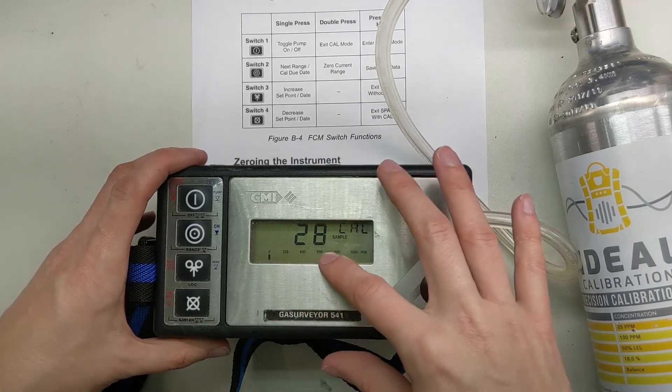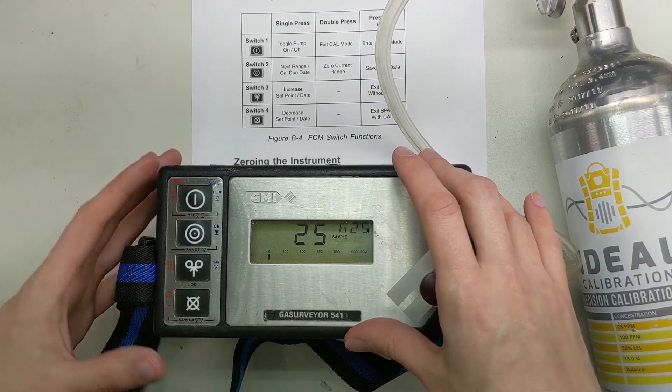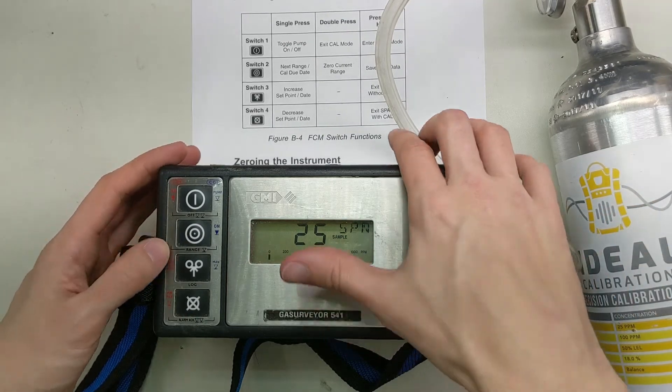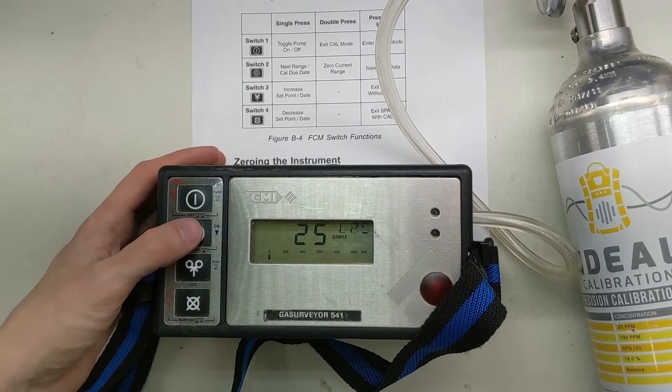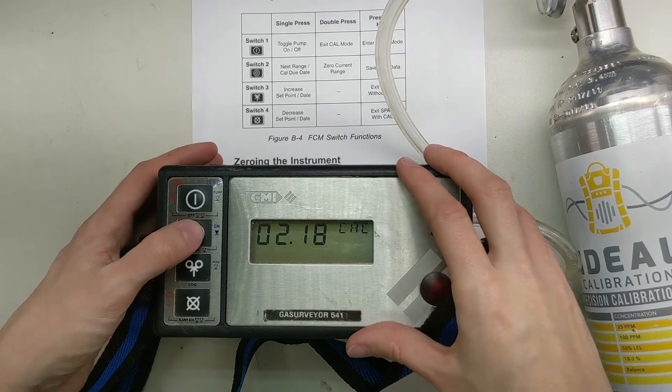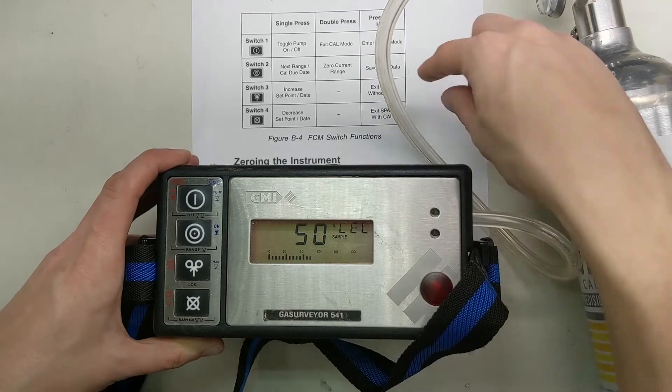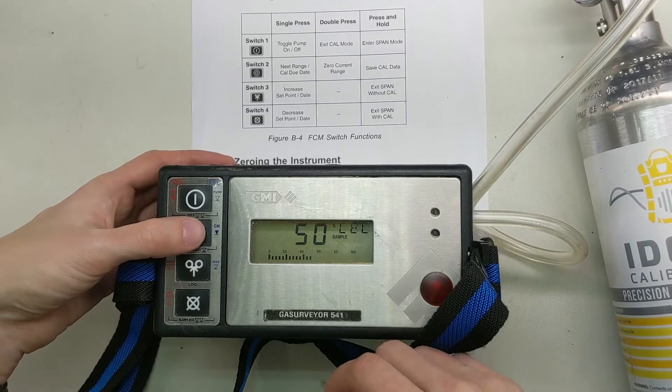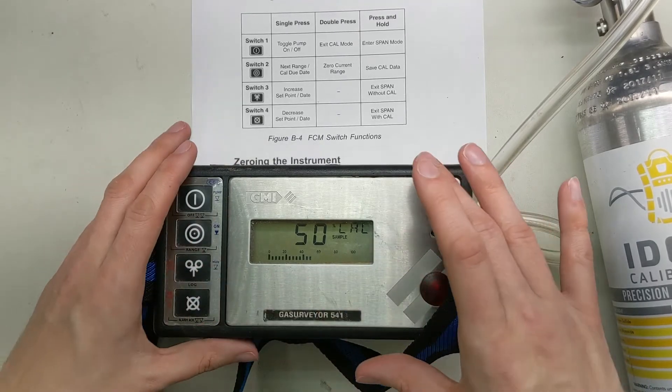Now we're going to press one time, go to H2S. Now it's seeing 28. We're going to go into span mode, press and hold. This is 25, that's what we want. We're going to save this Cal, exit span with Cal. Good deal, 25. Now next mode brings us to the date. Now we're back to the beginning. Now this is an important step to do now. We need to save Cal data. Press and hold this button here. And now it has saved the Cal data.